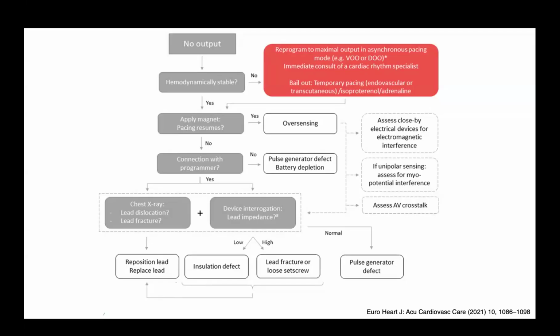dislocation or lead fracture. Sometimes there might be a micro-dislodgement, but that doesn't typically end up with no output. Maybe it requires a higher threshold, but no output is typically a sign of significant dislocation or dislodgement of the lead. If this happened, then the lead has to be either repositioned, or if it's fractured, it has to be replaced. In either case, if there is high impedance or low impedance, where we are concerned about lead fracture or insulation defect, then the lead has to be replaced.